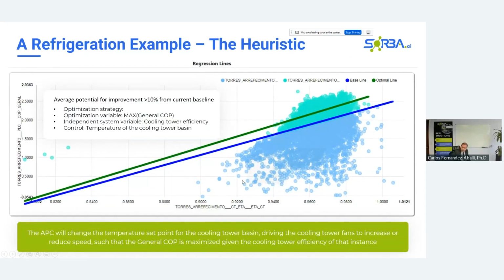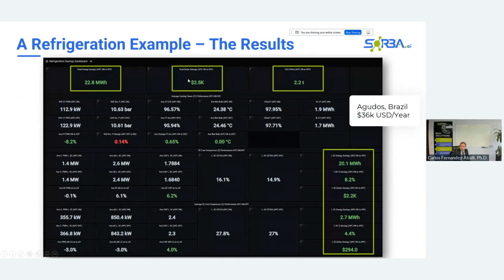Okay, here's another heuristic. This one is looking at the effectiveness of the cooling tower versus the general COP of the plant. This was implemented in Agudos in Brazil. In a 15-day period, we saw $2,500 in savings, which could be extrapolated to $36,000 of savings in the year. And this application, after being implemented, had a payback of around a year. So we were very happy with this result.